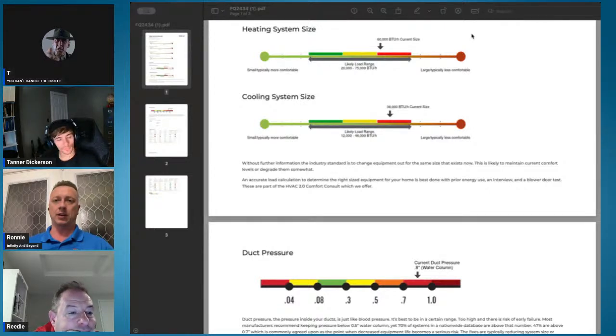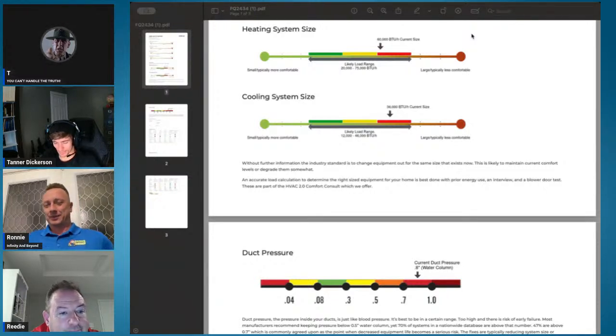It was a heat pump, but second stage of cooling wasn't hooked up. It was set only first stage and ran. It had been running at 63%, keeping it 68 degrees on a 90-degree day. Like it's still oversized. We put this into second stage, it's going to shut off, and then you're not going to get any dehumidification.